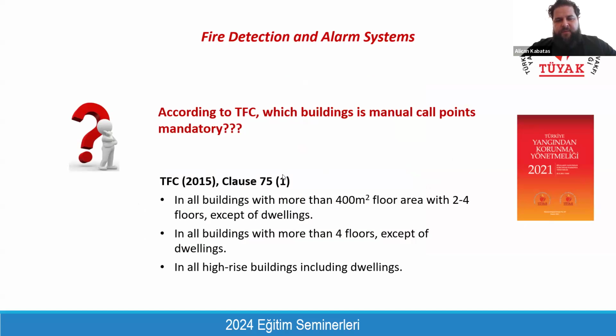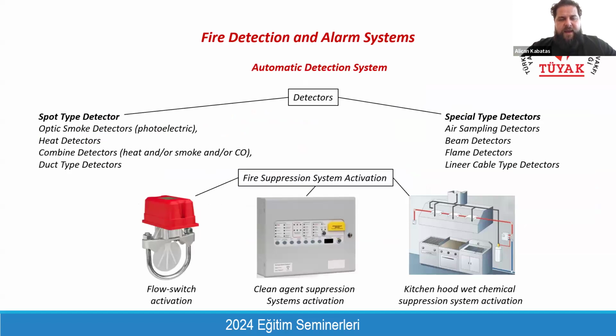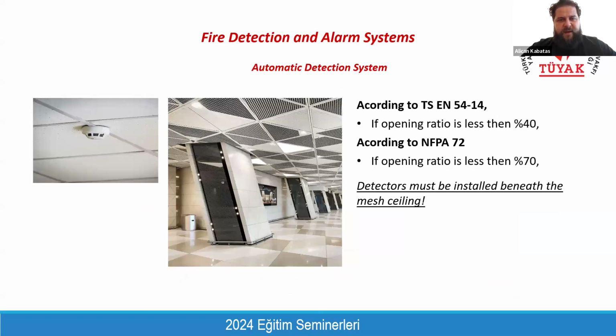But as architects, you will probably be responsible for high-rise buildings. These systems are mandatory for high-rise buildings. And the main schematic of the fire alarm and detection system is that we will have some automatic detectors. We will have some alarm indication devices such as flow switches to understand if there is a flow, or we will have some kitchen hood system activation modules. Also, the same for the clean agent. It means we are supervising all of the fire suppression and fire detection systems, and we will be alerted in case of any activation or failure.